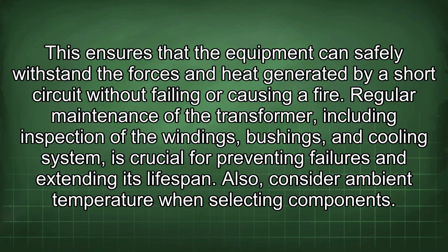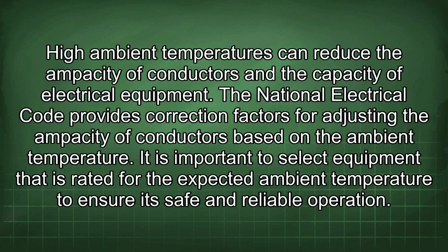causing a fire. Regular maintenance of the transformer, including inspection of the windings, bushings, and cooling system, is crucial for preventing failures and extending its lifespan. Also, consider ambient temperature when selecting components. High ambient temperatures can reduce the ampacity of conductors and the capacity of electrical equipment. The National Electrical Code provides correction factors for adjusting the ampacity of conductors based on the ambient temperature.